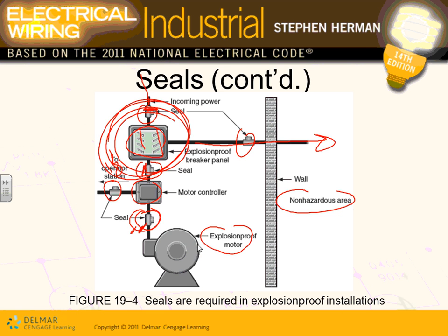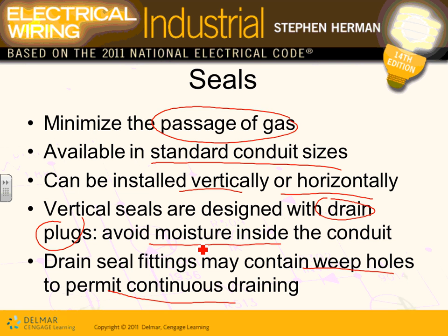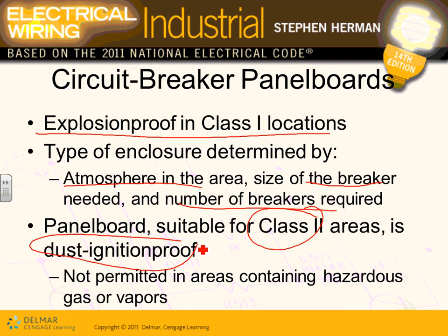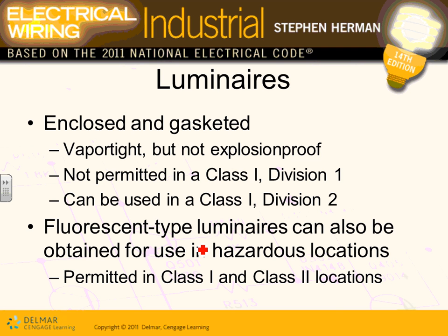Okay, so we got that one. The seals, drain seals may contain weeps. Talked about these. Okay, luminaires. When you put luminaires, guys, in an explosion-proof location, a lot of them are enclosed. You look at enclosed and gasketed, vapor tight, but not explosion-proof. If you put them in a gas area, you have to be explosion-proof. If you put them in a Class 1 Div 1, the fixture has to be explosion-proof. If you put them in a Class 1 Div 2, they don't have to be. They have to be vapor tight, enclosed, and gasketed.